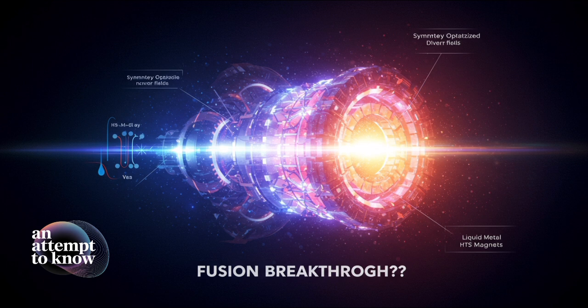They claim these algorithms can predict a quench about 30 seconds before it happens. That's an eternity in magnet time, enough to react, initiate a controlled ramp down of the current, or take other preventative measures. It's proactive, not just reactive.